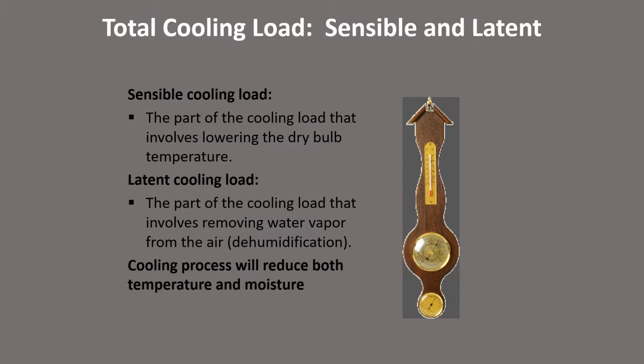So yeah, just going over the definitions of sensible and latent cooling load. The sensible is that part of the cooling load that involves lowering the dry bulb temperature. And dry bulb, this means a regular thermometer. If you put it in your house or you put it outside, that's the dry bulb temperature that you're getting. The latent load, that's the part of the cooling load that involves removing water vapor from the airstream. And in muggy climates, this is critical.